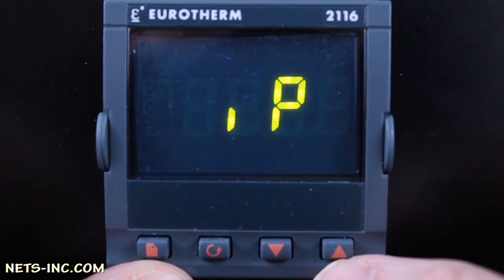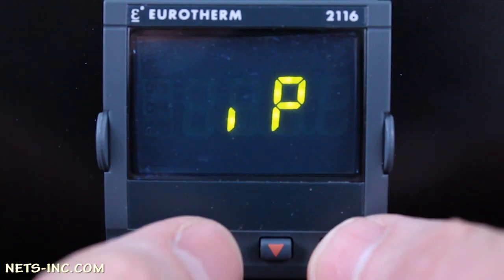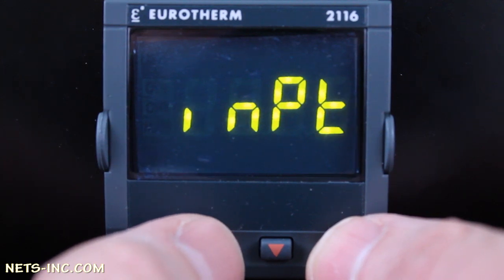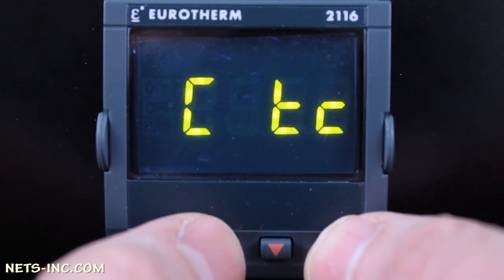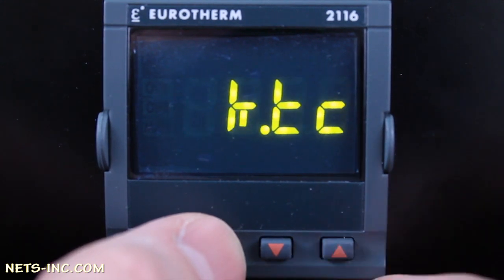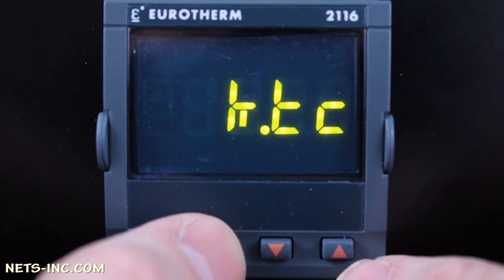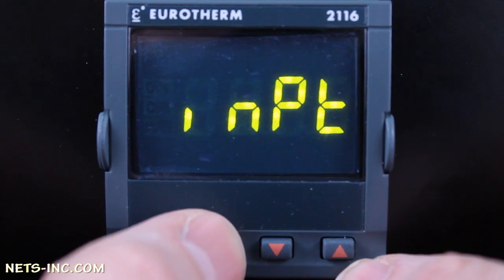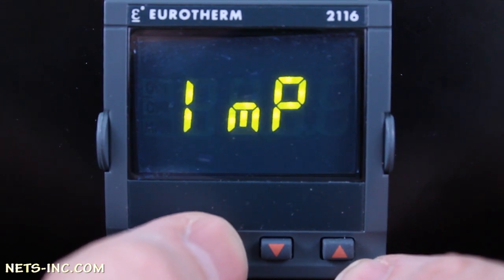Next, press the Page key once to advance to the IP list. This is where you set up the type of thermocouple input sensor you are using. For this example we will be using a type K thermocouple. Press the Scroll key once and the display will read INPT. Press the Up Arrow until the display reads K.TC. Press the Scroll key repeatedly until the display reads IP once again.